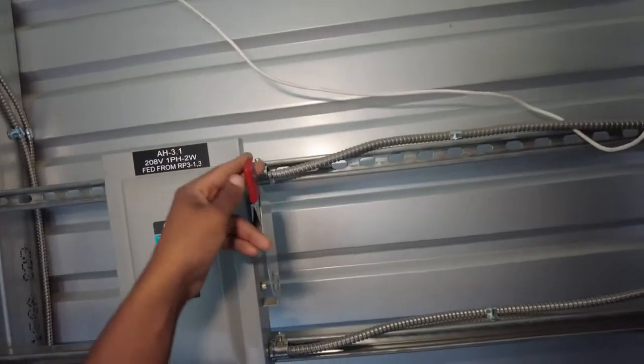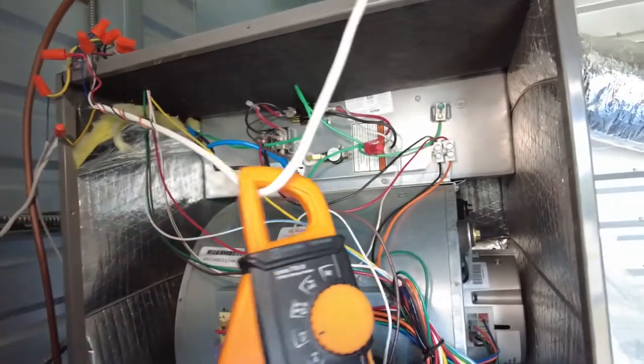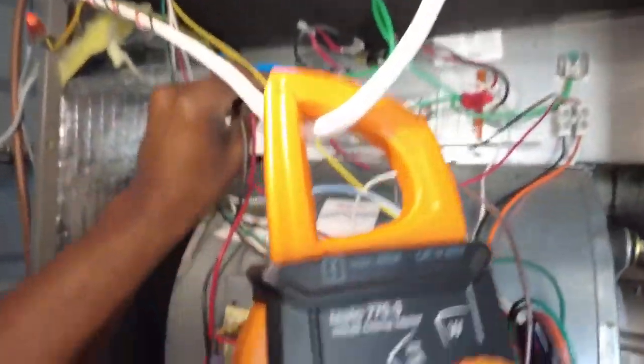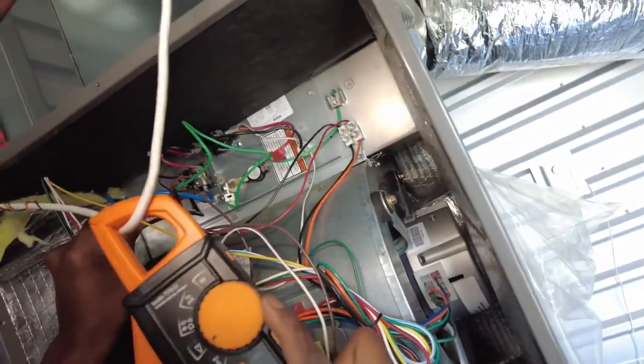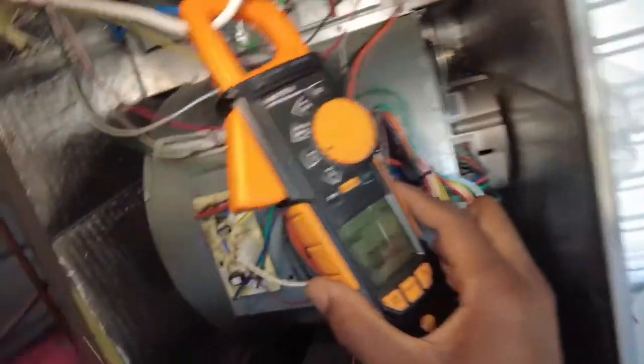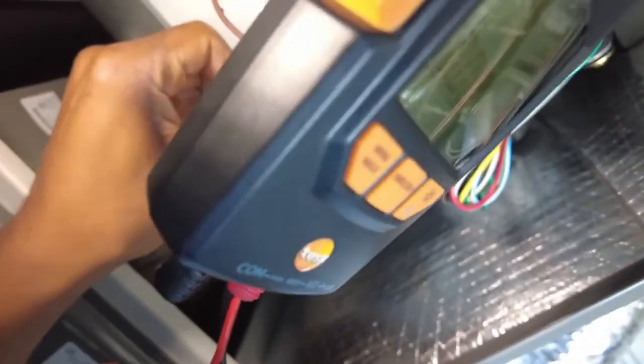So we'll go ahead and cut our power here. 208, single phase. So we're just going to go ahead and cut that. Always check our power. I think that it just cut off on me like that because, you know, what else is doing by itself. Zero volts. This should be a quick, simple, could have done this hot, but I don't want to. Pop that under the 208.